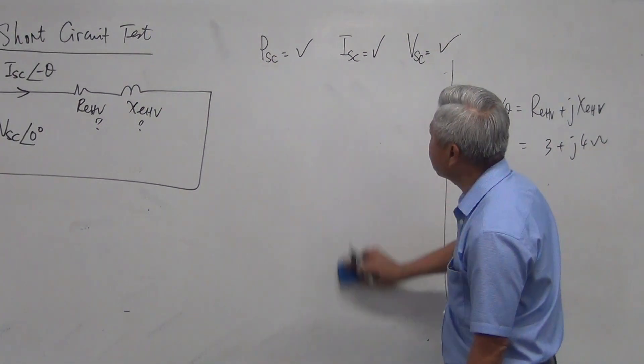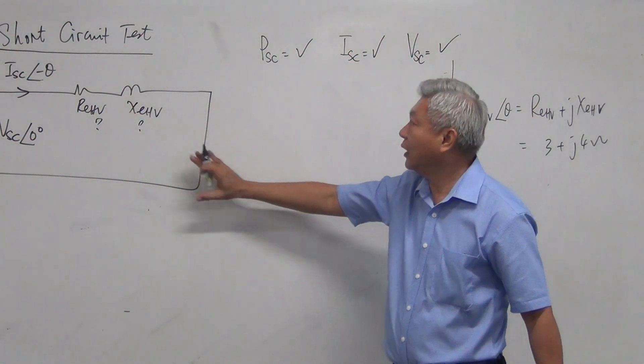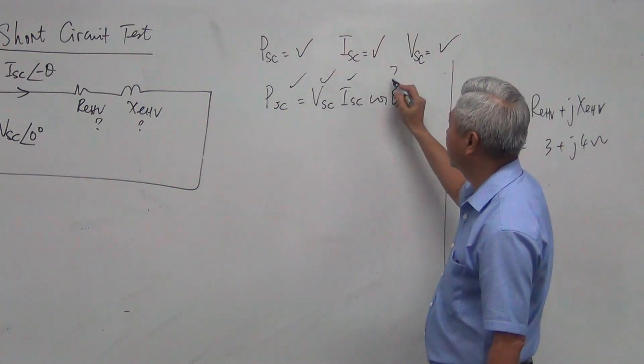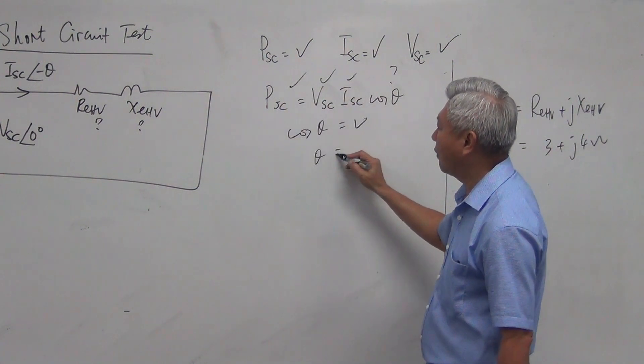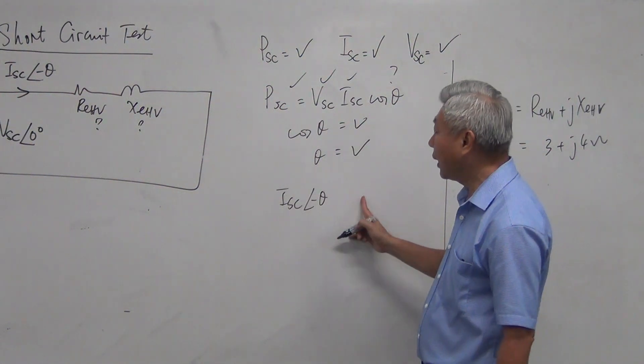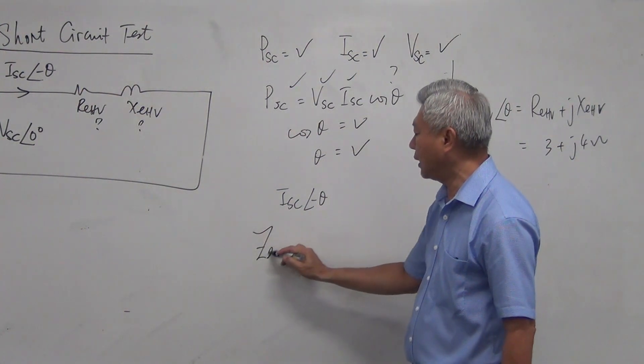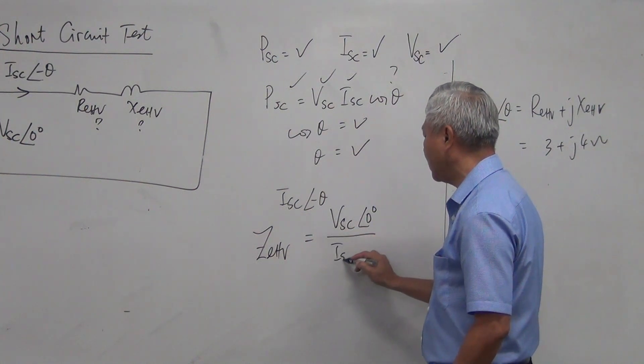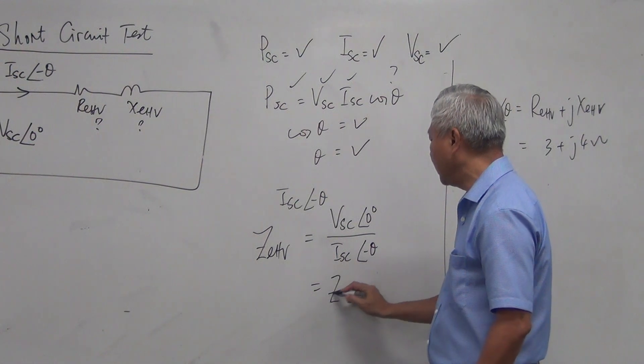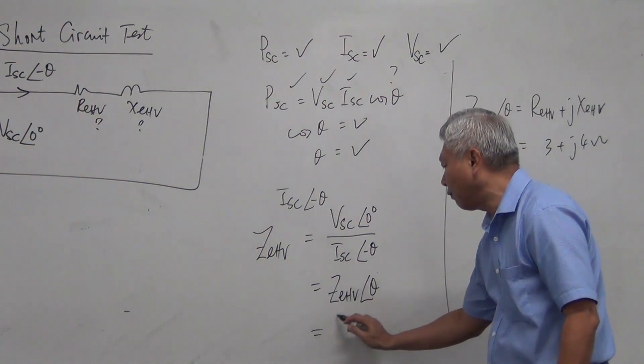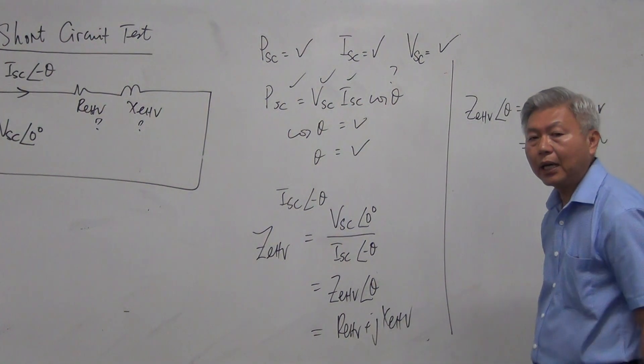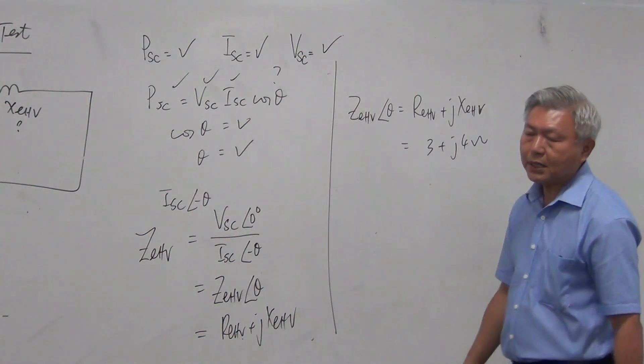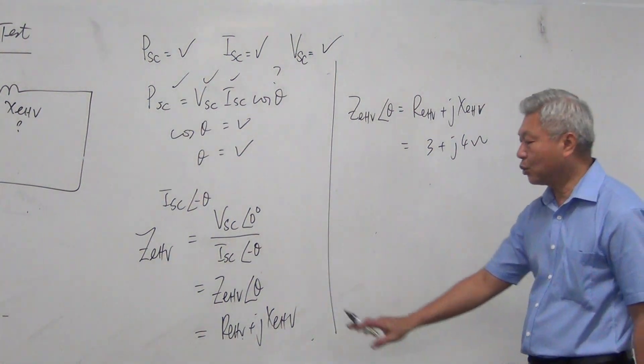Short circuit test: the experiment is done on the high voltage side. The first step is P = V × I × cos θ, so cos θ can be found, then theta can be found. Substitute theta into the current with a minus sign and leave it in polar form. Go straight to find the impedance, which equals VSC at 0° divided by ISC at minus theta. Your impedance is in polar form; then make it into rectangular form and the two parameter values are revealed. These two parameters — REHV and XEHV — are usually small values.